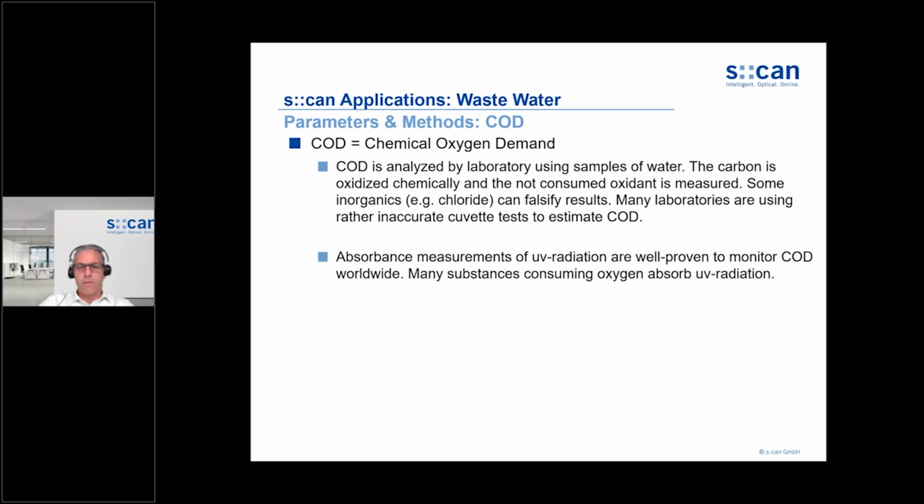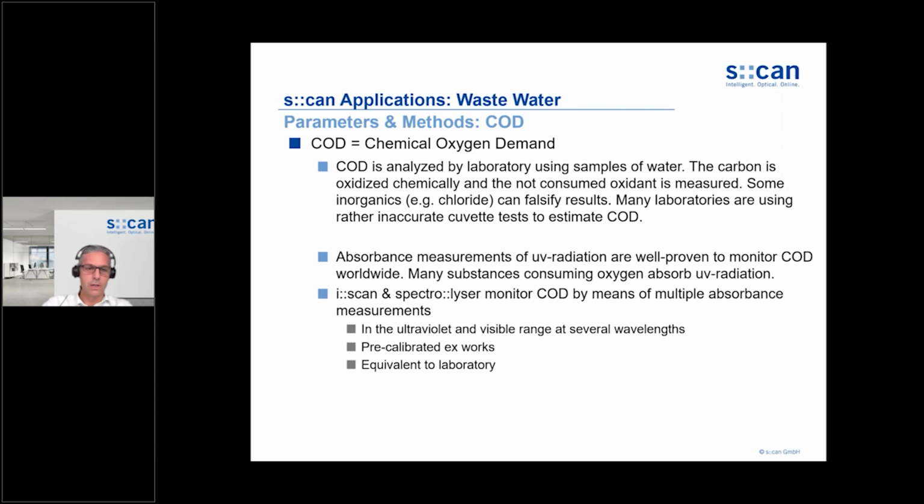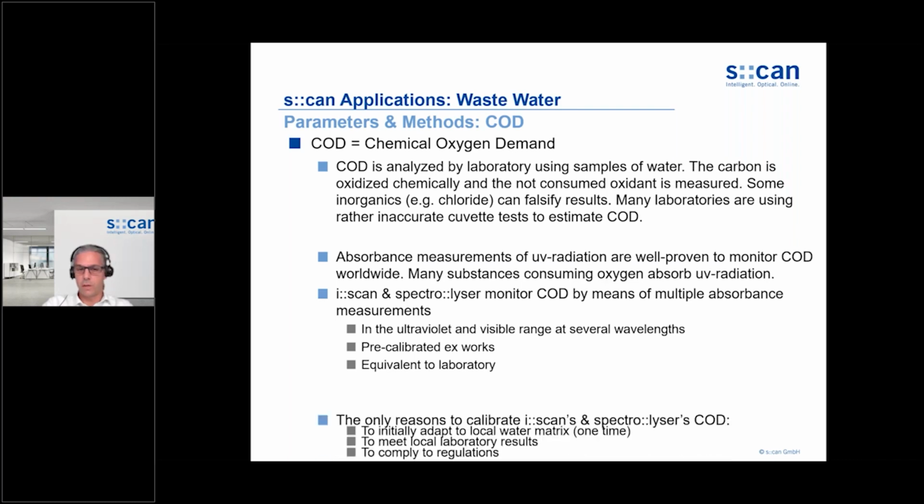Absorbance measurements are well proven to monitor COD worldwide. Many substances that are consuming oxygen are also absorbing UV radiation. That's why we can monitor it with our instrumentation. The i::scan and the spectro::lyser monitor the COD by means of many wavelengths of absorbance in the UV range and in the visible range. It is pre-calibrated ex works and is equivalent to laboratory.